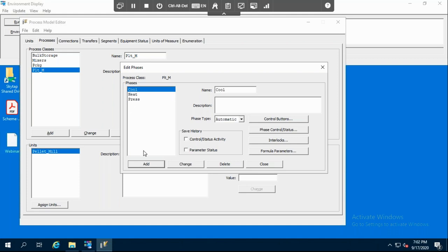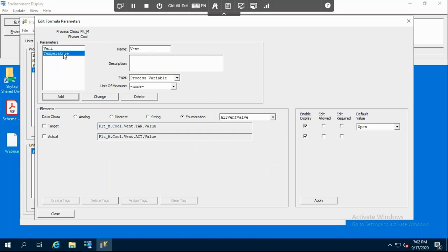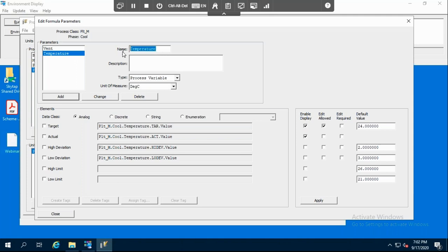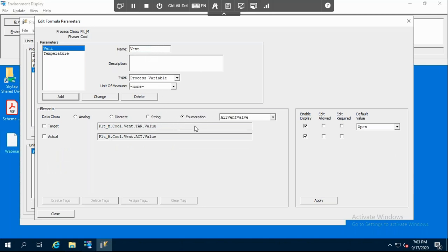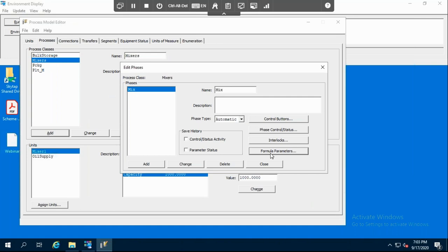In order to specify the temperature of the cooling, we have to add a parameter. I want to specify the temperature at which I want to cool my product — we add a parameter called temperature. We want to see the target, the actual, the high, and the low deviation. I already specified the cooling temperature as 24 degrees C, with a high deviation of two and a low deviation of three, so the maximum will be 26 and the minimum will be 21 degrees C. For the vent, which is an enumeration, we click on enumeration, select target and actual, and create tags.